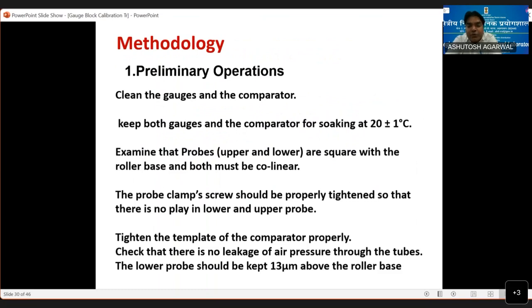Primary operation, what you can do: clean the gauge and the comparator first, don't turn on, first clean. Always keep both gauges and comparator for soaking at least one day, one night. Examine that the probe upper and lower parts are square with the roller base and both must be collinear. Check by doing this that these must be in the same position. Okay, the probe clamp screw should be properly tight. It should not be loose because you have to move like this. Okay, when you do, tighten so that there is no play in the lower and upper probe. Tighten the template of the comparator properly. Check that there is no leakage of air pressure through the tubes.